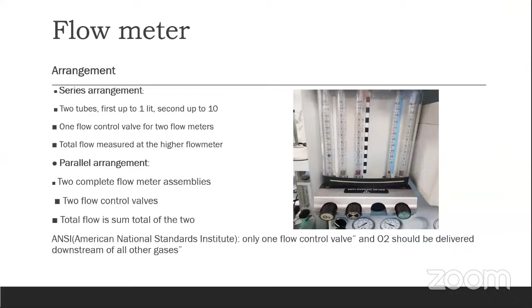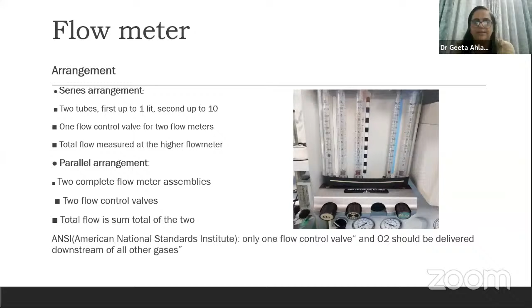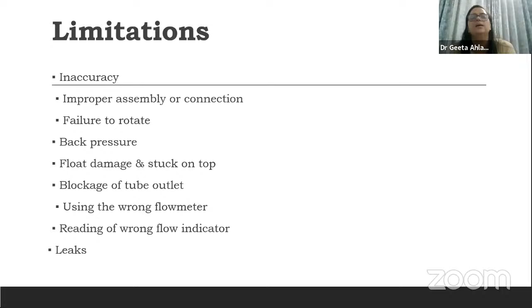So as I told you, these knobs are gas specific, color coded, touch coded, and at a minimum distance apart. The arrangement of these flow meters could be in series, where a lesser flow, especially for oxygen, can be in one tube, which is in series in continuation with the tube that gives you more flow. So the flow meter reading would be at the top of the higher flow meter. In the case of other gases, it could be a parallel arrangement. Now these two have their limitations, like there can be an inaccurate reading, or the float or the bobbin that rotates sticks on the top, or there's blockage of the tube, and there can be leakages.